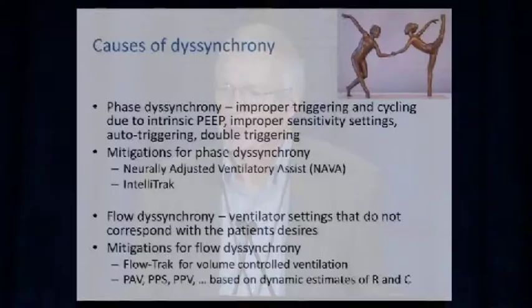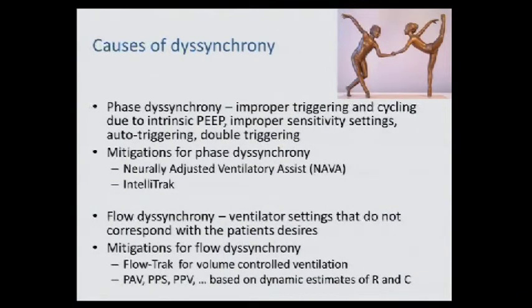So phased asynchrony is due to improper triggering and cycling. Intrinsic PEEP is a very common reason for that. Improper sensitivity settings on the ventilator can also cause it to auto-trigger. If the sensitivity is very fine, it's actually auto-triggering even off of cardiac oscillations that it picks up.